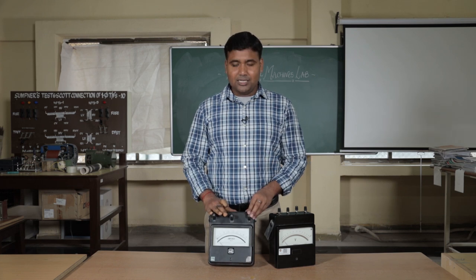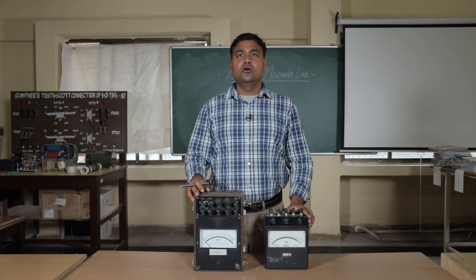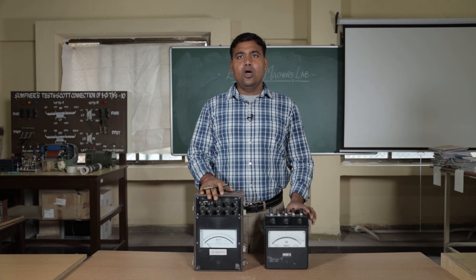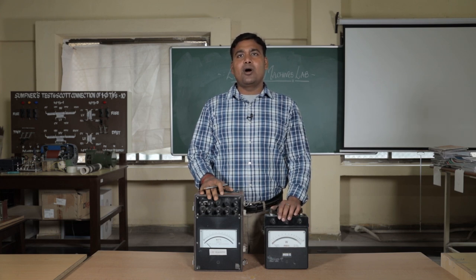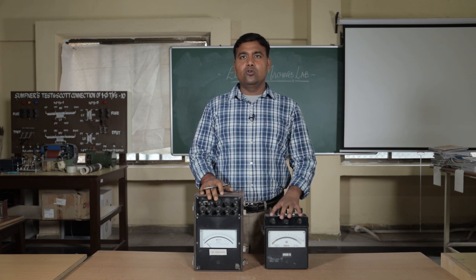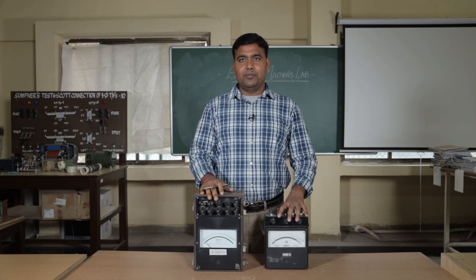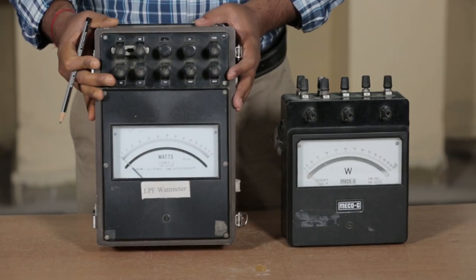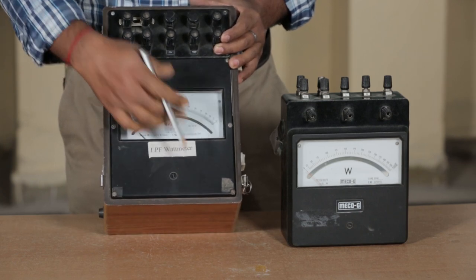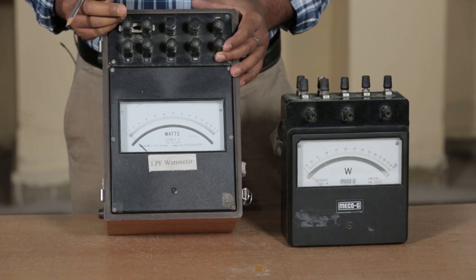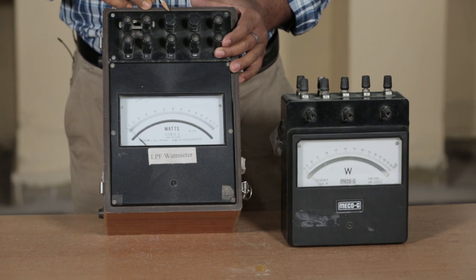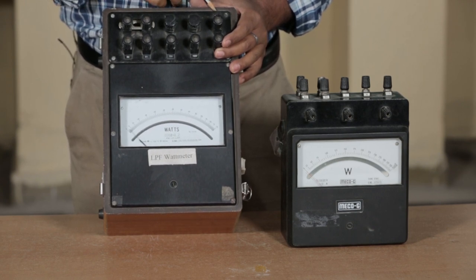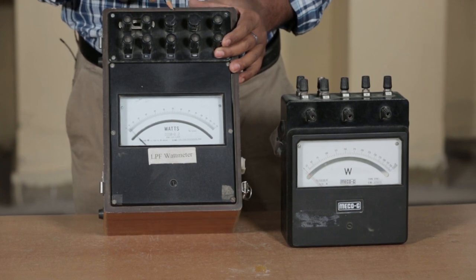To measure power, we require a wattmeter. Wattmeter can be of two types: low power factor wattmeter or unity power factor wattmeter. Power factor can vary from 0 to 1, where 1 indicates unity power factor. Whenever we want to measure at unity power factor condition, we use the UPF wattmeter. To measure at low power factor, we use the low power factor wattmeter. We have a current coil and a pressure coil (voltage coil) in the wattmeter, whose terminals are represented by L, M, and a common point.